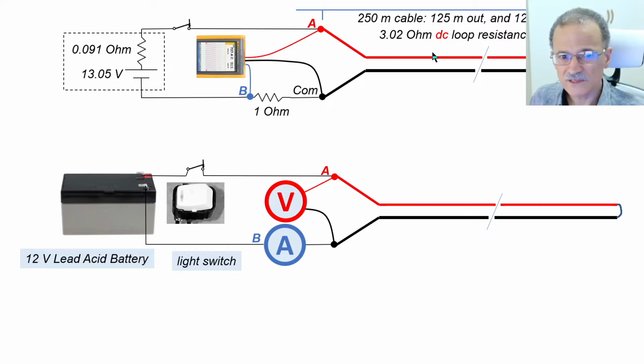This resistance of the copper loop, the 250 meters copper loop, was measured to be 3.02 ohms at that temperature of the day. The first thing we're going to calculate is what the end current will be once you've flipped the switch and all the effects have settled.